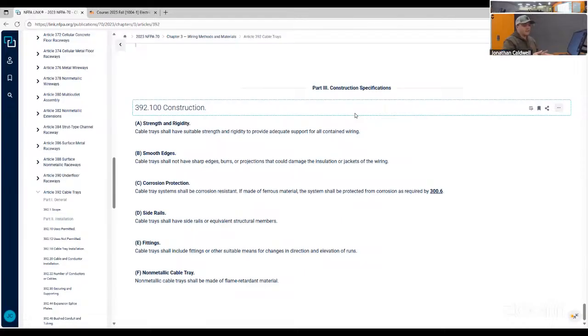The reason why we ground the supports of our tray is because most of it is typically built with the tray. Like I said previously, it is essentially another tray underneath our tray. So if something happens with our tray and a cable somehow gets nicked, I don't think that will ever happen with the cable that we use, but if it does get nicked and it hits that steel, it needs an effective ground path to ground to, right? So that's why we still run a 4/0 ground through there and then bond it. I think it's like every 50 feet or whatever.